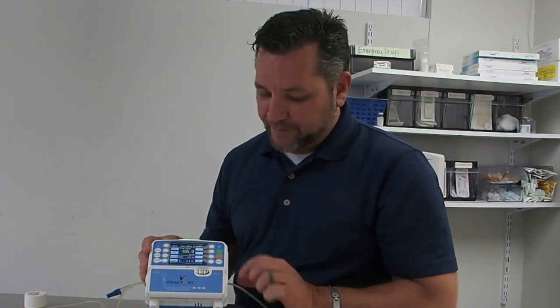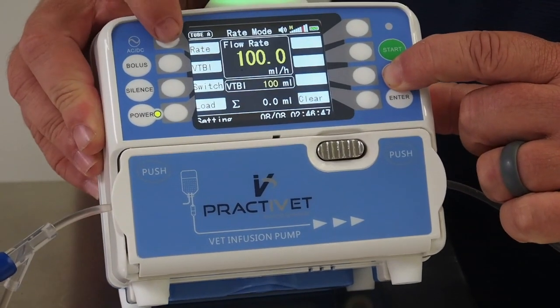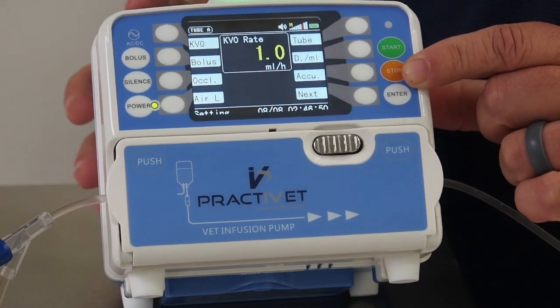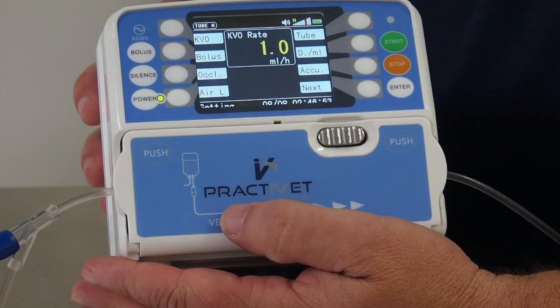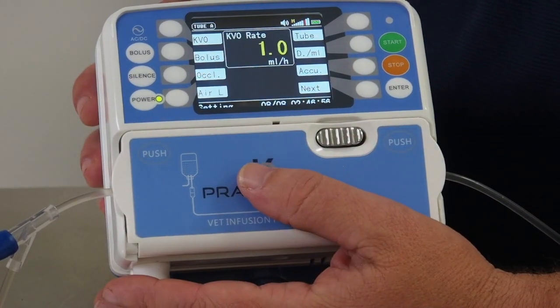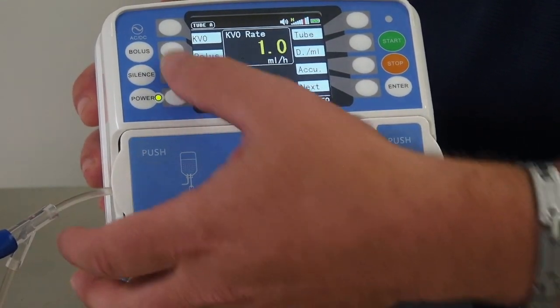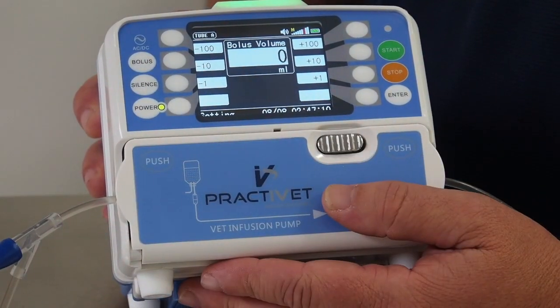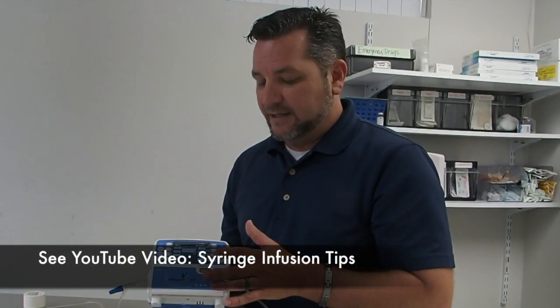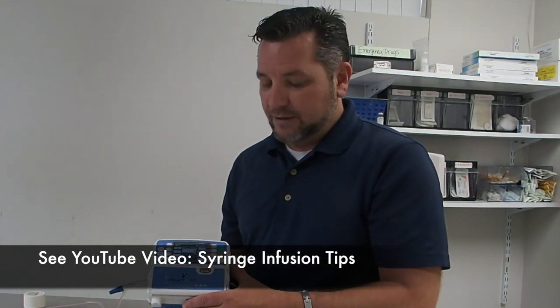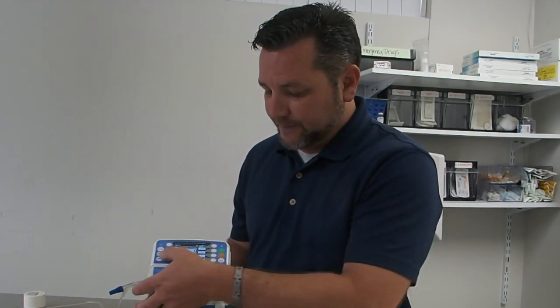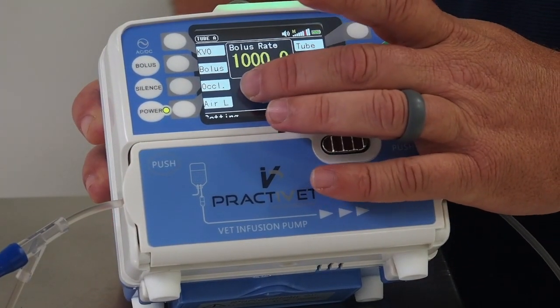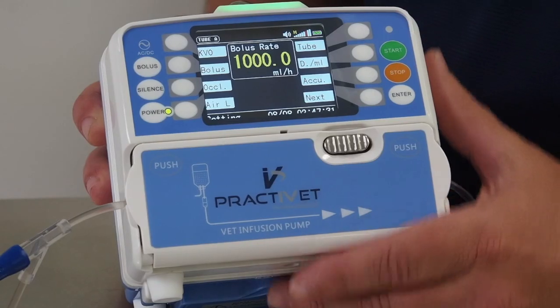I'm going to discuss how to get into the settings menu of the Practivet infusion pump. You want to hit the stop button and the top left soft key. This brings you into the settings. You can program your KVO, or keep vein open rate, from between 1 and 5 mils per hour. You can program your bolus rate from 300 mils to 1200 mils per hour. And you can also set your VTBI. And we'll discuss this later, how you can set it to the amount you have in a syringe that you want during a syringe infusion. You can also change the tolerances with your occlusion alarm and your air in line alarm.